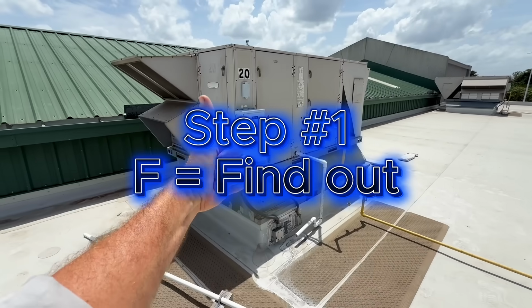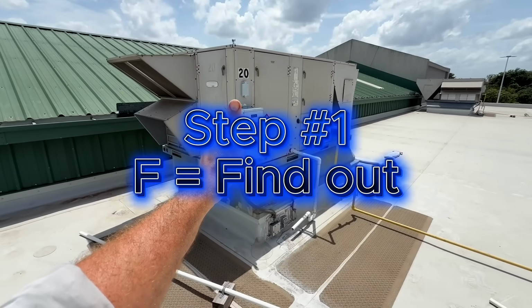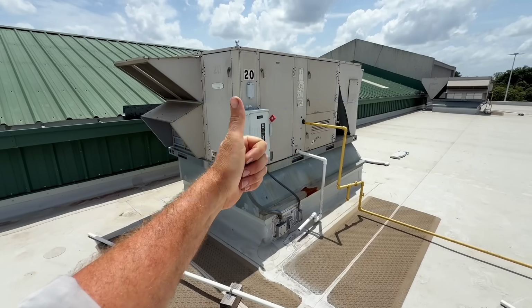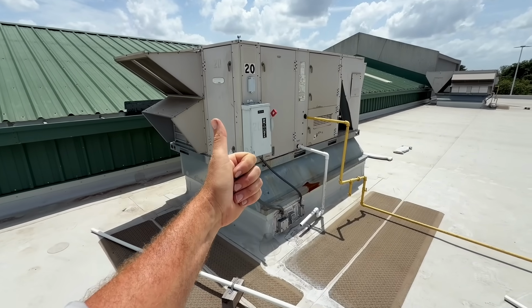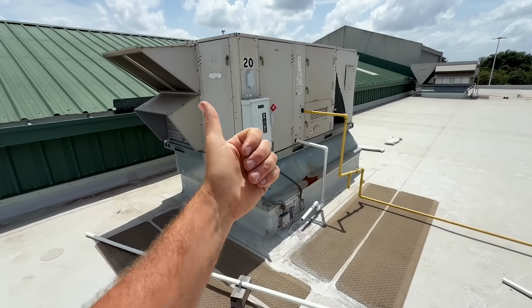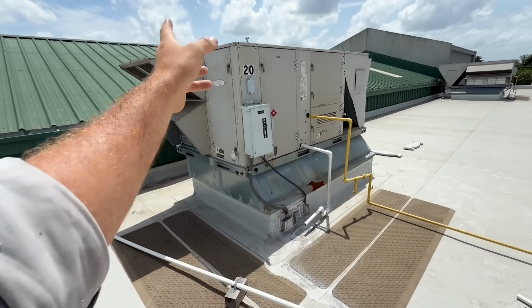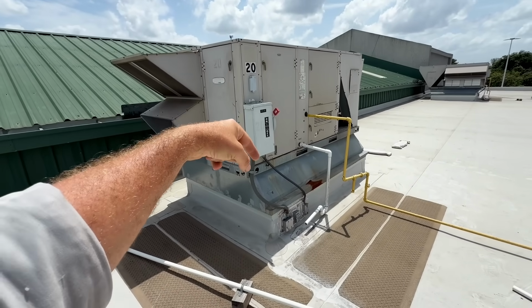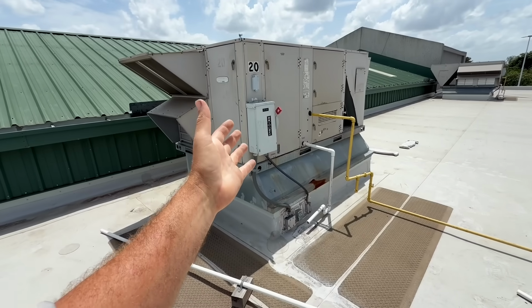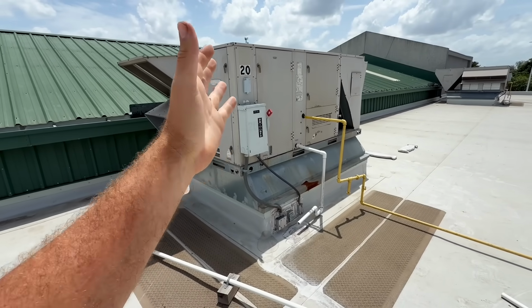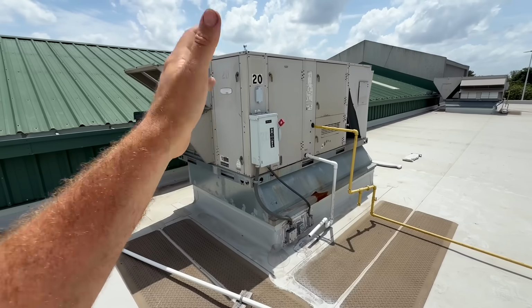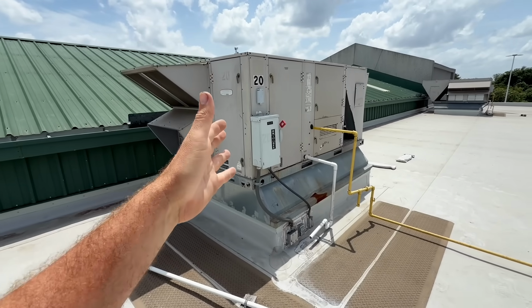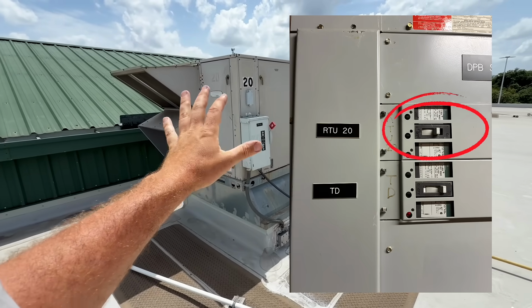Step number 1, obviously, in fixer is the F, which is find out what's going on. You do that by reading a job description and talking to the customer. In this case, we arrived, they already showed us where the unit is downstairs, and then they told us that the reason they found it is because their fire system is telling them that the smoke detector can't be detected, and that's how they found out that the breaker was tripped.